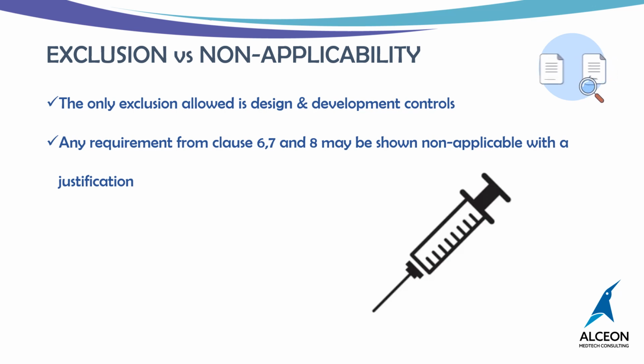So, for example, if you're a syringe manufacturer, requirements related to installation and servicing may not really apply to that product because it doesn't fit the intended purpose of the product. So, you can show installation and servicing requirements as non-applicable within your quality management system. Now, if you see, the exemption is not given from the requirements of clause 4 and clause 5 because clause 4 sets out basic principles of quality management system and documentation requirements, and clause 5 is about management responsibility. So no requirements can really be excluded or can be shown non-applicable from any of these two clauses.